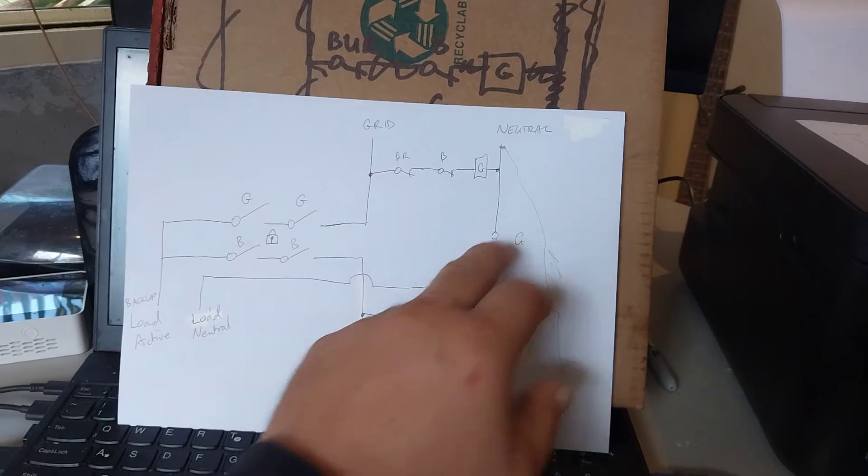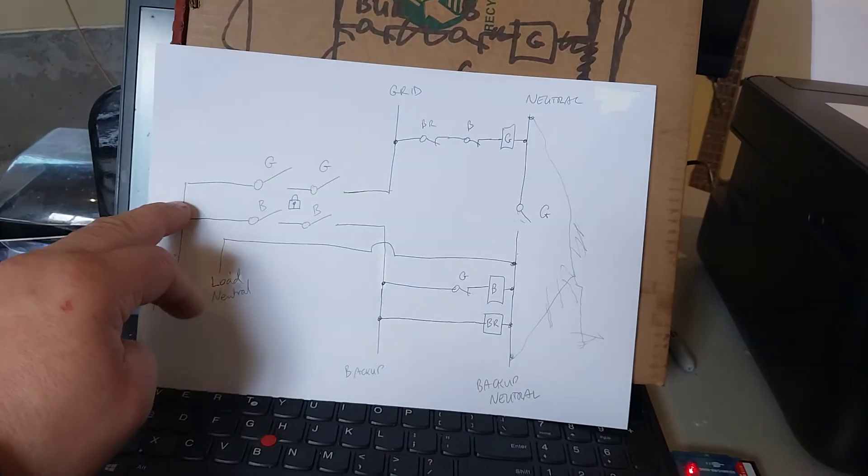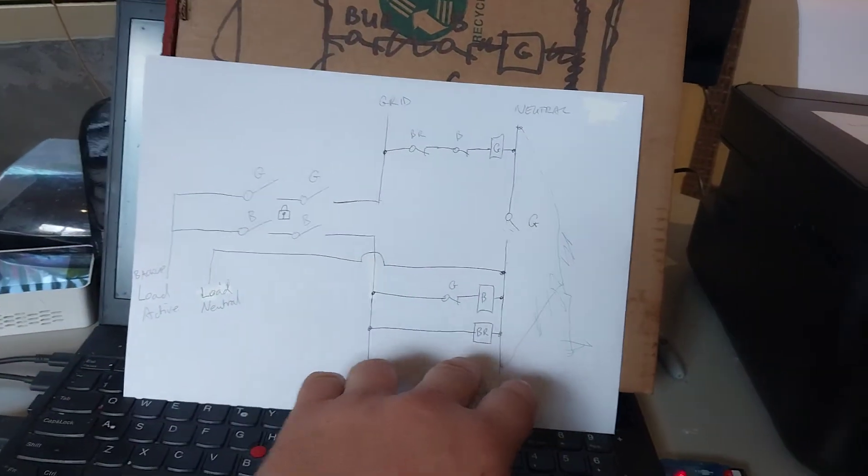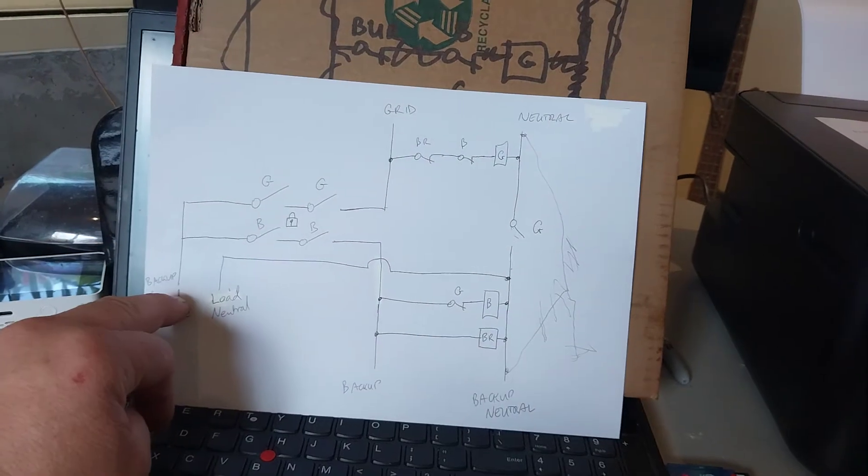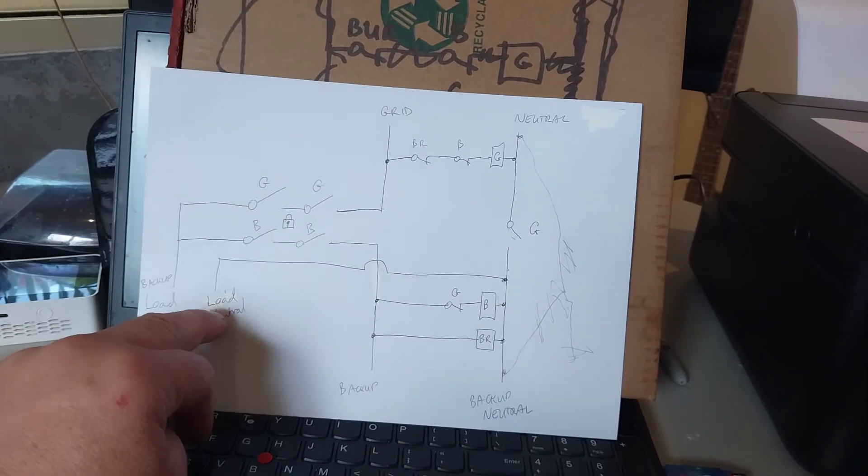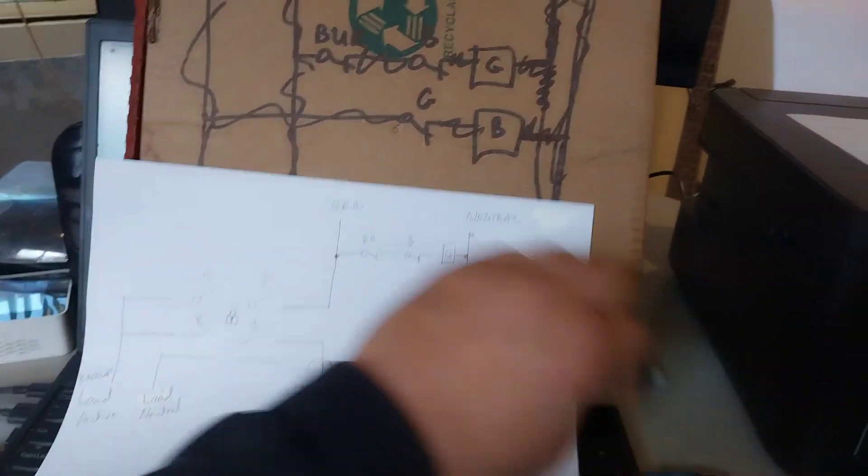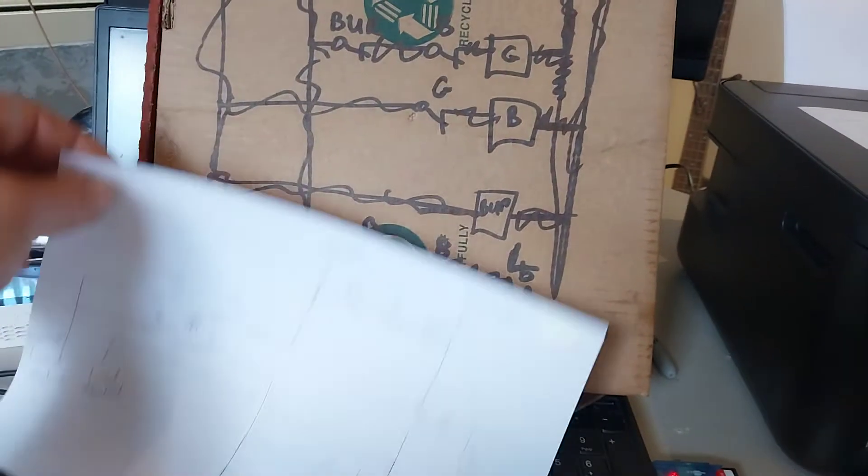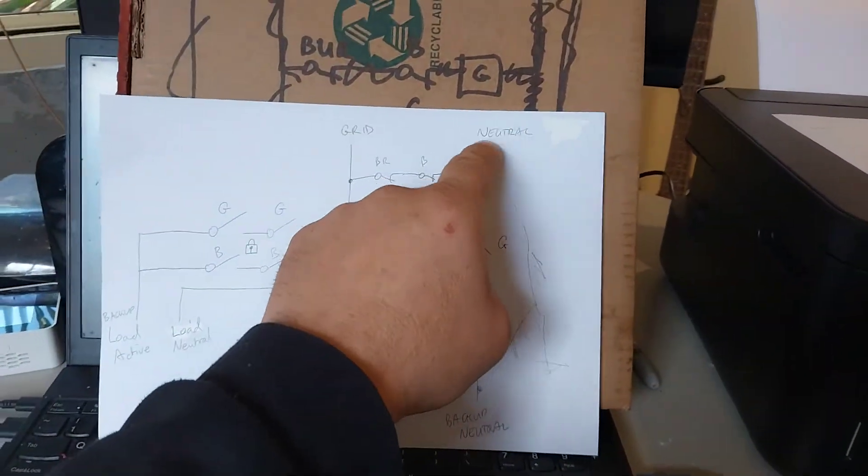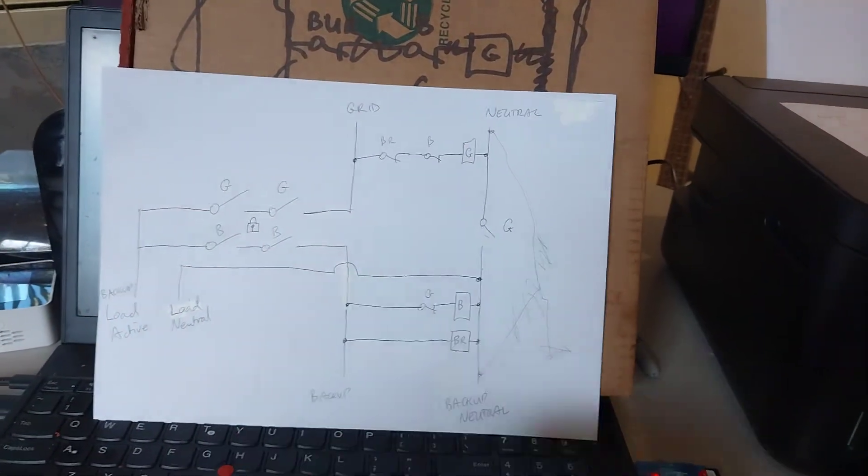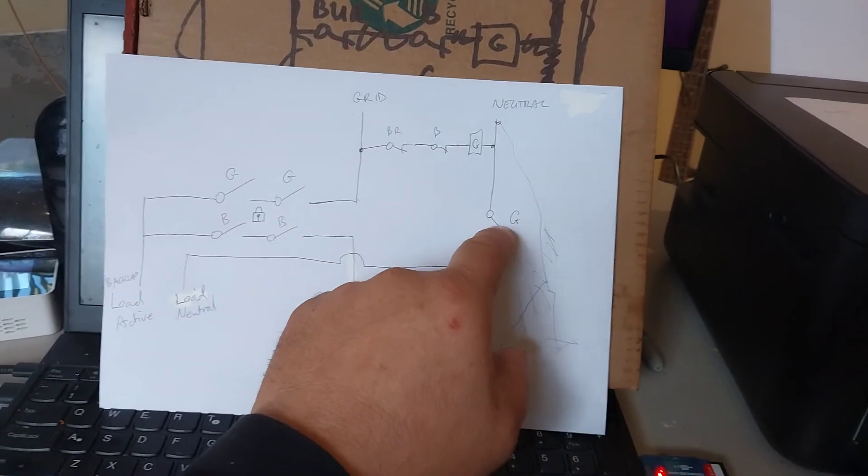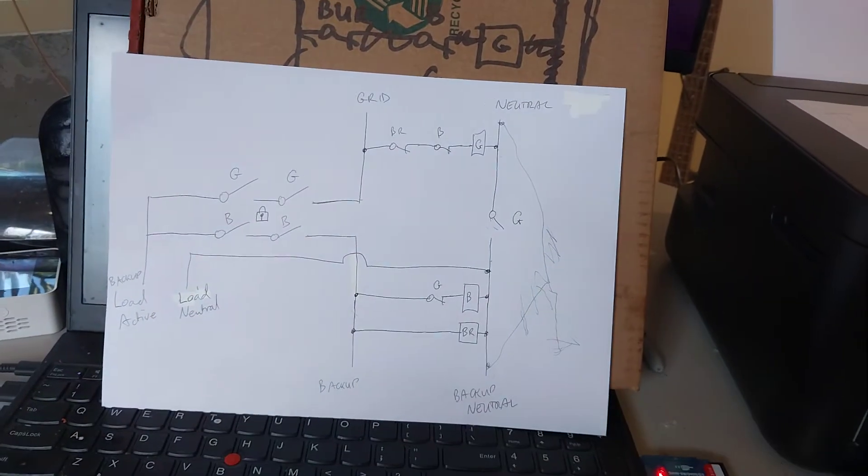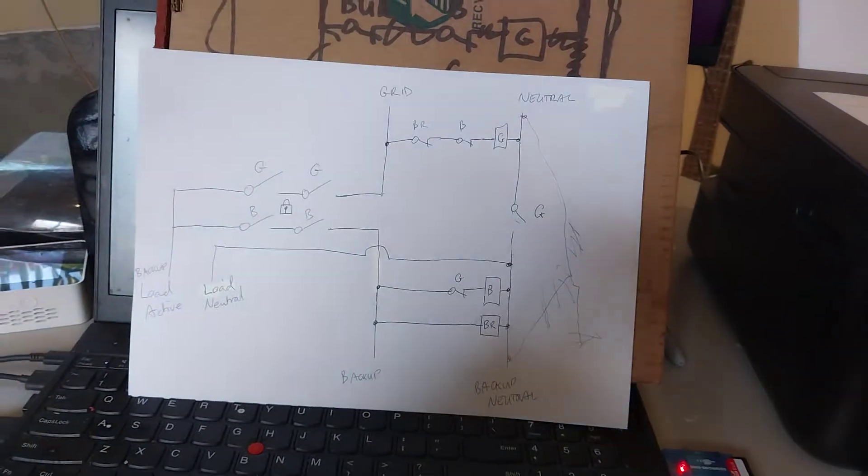But when we have grid supply in the event that this equipment is failing for some reason, we also need the neutral to get back to the main neutral from the grid. So that's what that contact is for. Using the third pole of a three pole contactor there. That's pretty much it.